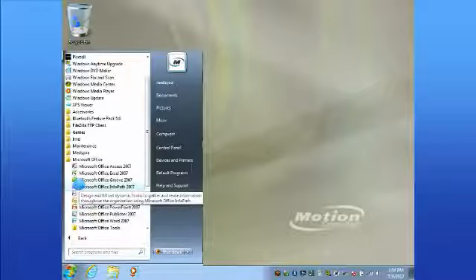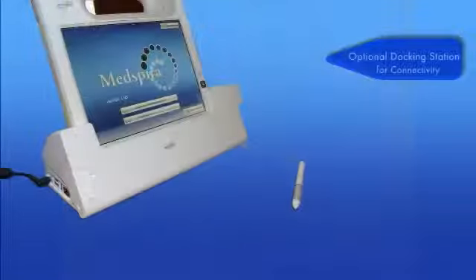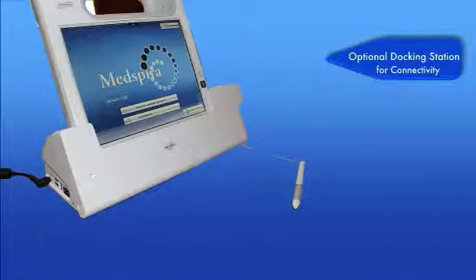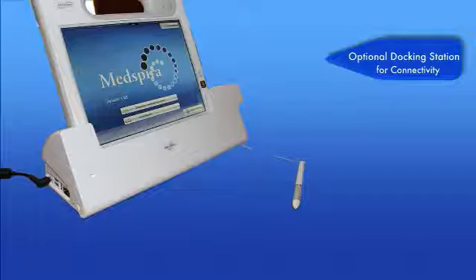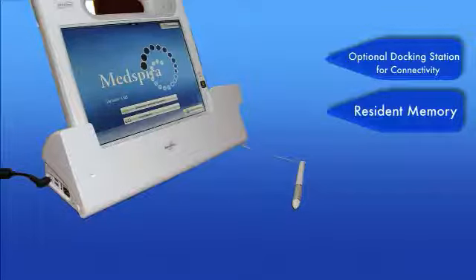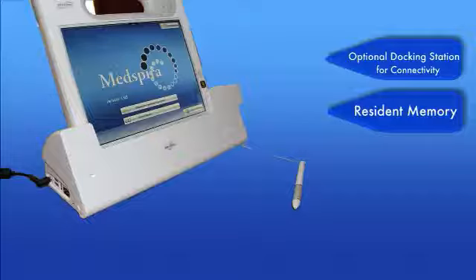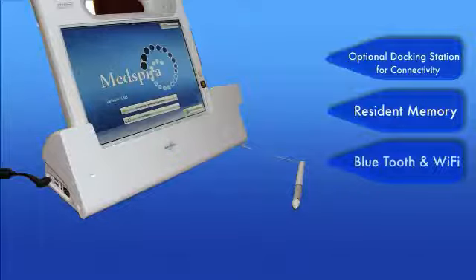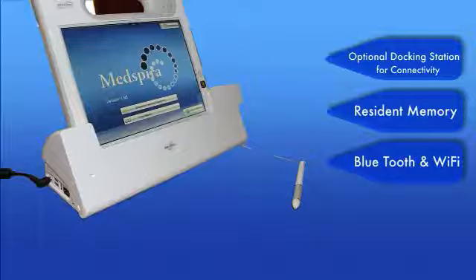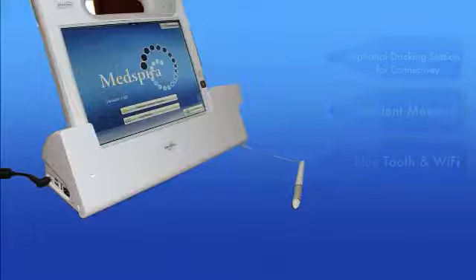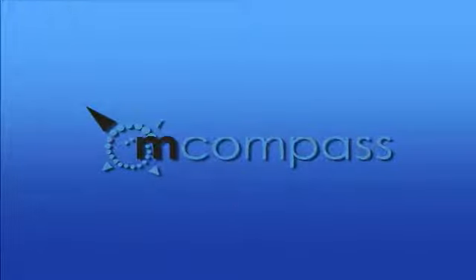Again, it's a fully functioning tablet PC that has wireless interconnectivity. The tablet PC has an optional docking station, so you can connect it through hardwire and use a separate keyboard and mouse if you choose to do that versus the pointer pen. It also has built-in resident memory that can be utilized in the system. It has Bluetooth to communicate with our wireless manometer fob, and it also has Wi-Fi. So if you happen to be at a remote location, you can connect to the internet via Wi-Fi. Thank you.